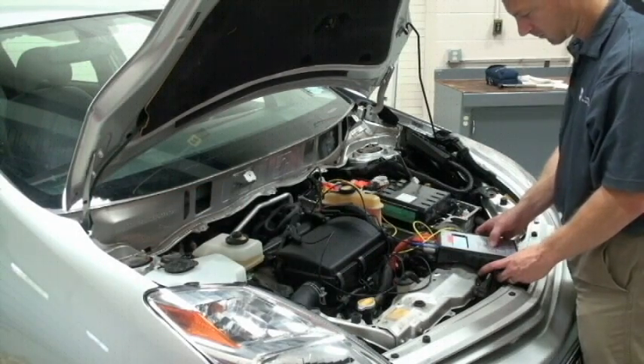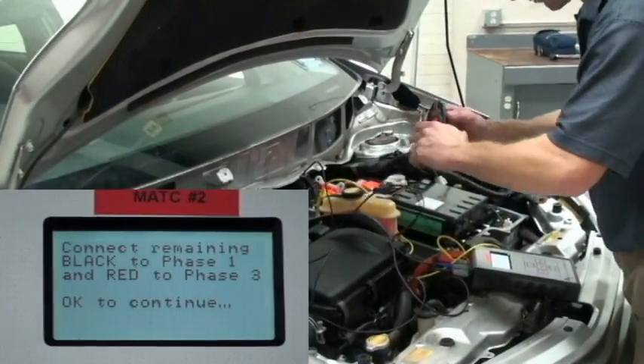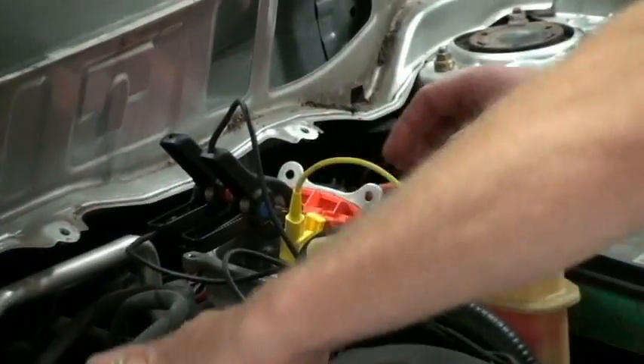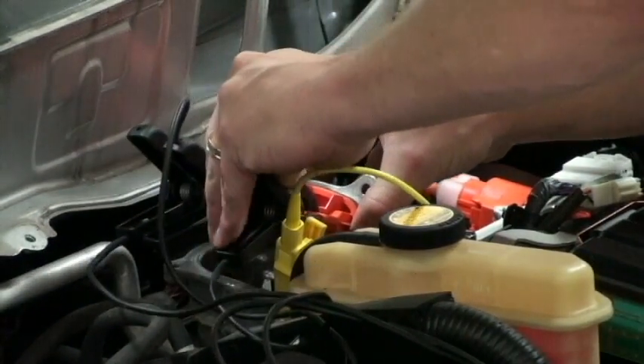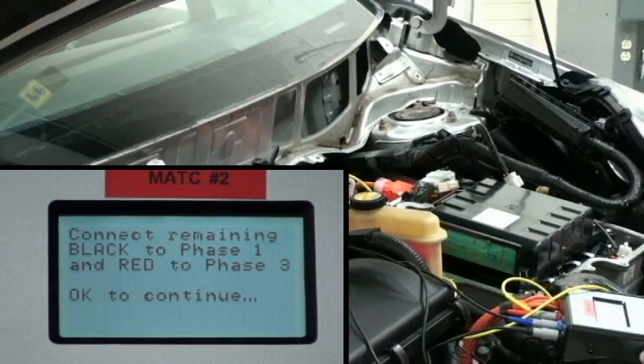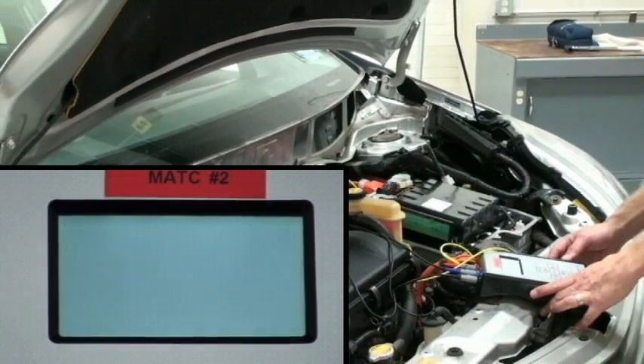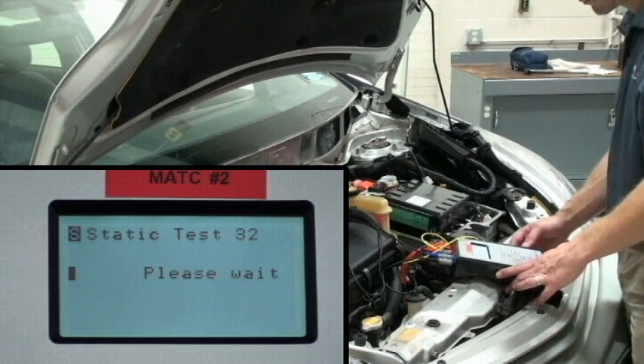Once the insulation resistance test and the dissipation factor or tan delta test has been completed, the remaining two test leads from the AT33EV will be connected onto phases A and C, or 1 and 3, to perform a battery of static tests. The static testing will include DC resistance, impedance, inductance, capacitance, current to frequency ratio, and phase angle. And the AT33 will then do comparative testing, which will compare the three phases against each other to determine the static motor condition. It's now testing phases 3 to 2, and then 2 to 1, and then finally 1 to 3. And now it will use that data, compare the phases against each other to find the motor static condition.